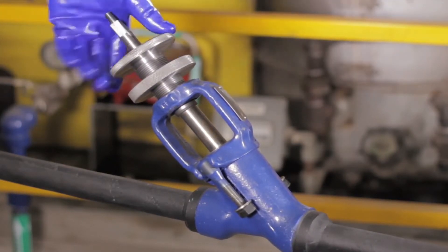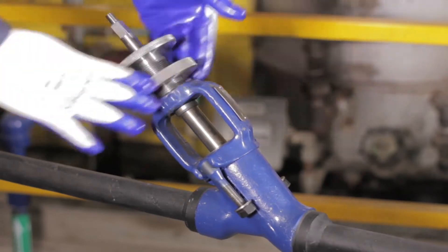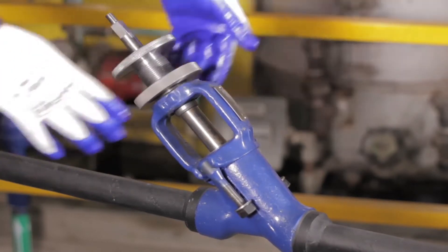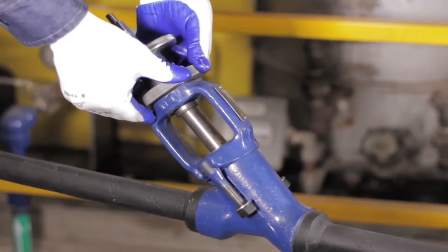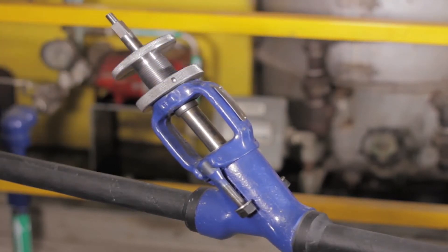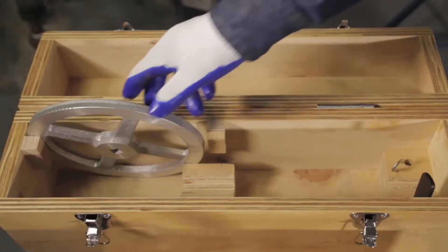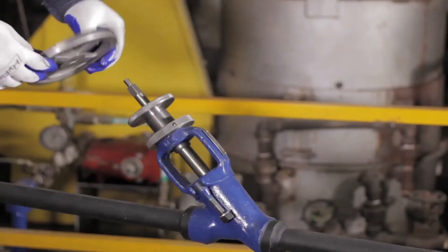The tool is inserted through the valve yoke. You should hand tighten the feed screw until the cutting blade contacts the valve seat. When the cutting heads make contact, tighten the lock knob to prevent the tool from taking progressively deeper cuts into the stellite material.